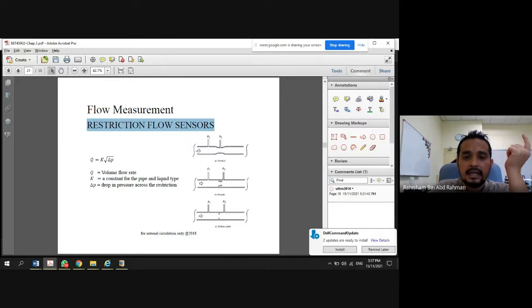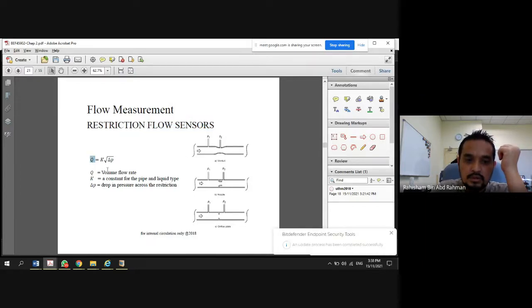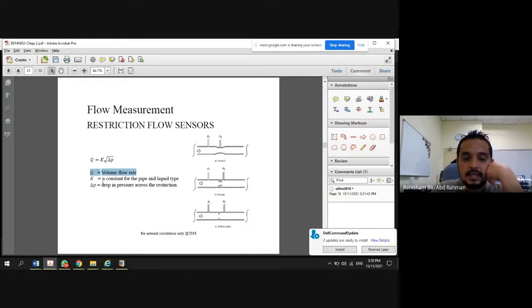As I explained before, there are some other options that have been introduced to measure the flow. One option is, if you can see here, there is a notch. Notch means that in the pipeline there is a point where the diameter is reduced, and then they put pressure 1 and pressure 2. Once you can measure pressure 1 and 2, you can calculate the Q, the volume flow rate.